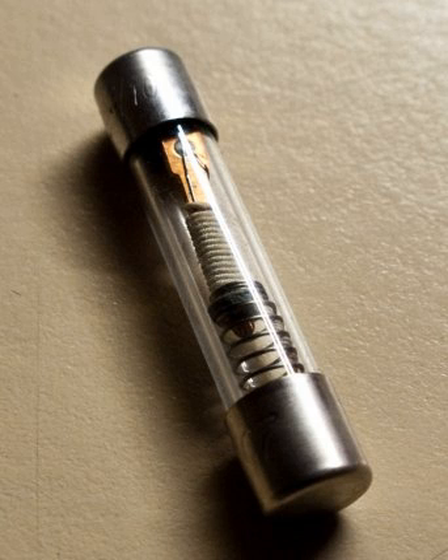Topic: UL 248 fuses, North America. In the United States and Canada, low-voltage fuses to 1 kV AC rating are made in accordance with Underwriters Laboratories Standard UL 248 or the Harmonized Canadian Standards Association Standard C22.2 No. 248. This standard applies to fuses rated 1 kV or less, AC or DC, and with breaking capacity up to 200 kA. These fuses are intended for installations following Canadian Electrical Code, Part 1 CEC, or the National Electrical Code, NFPA 70 NEC.